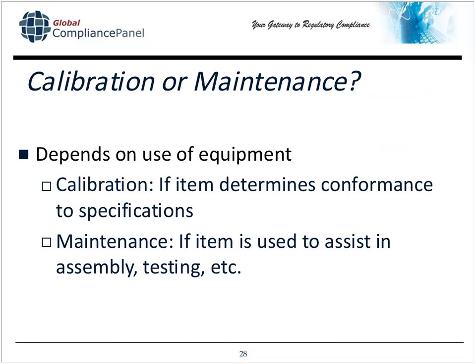Whether you maintain or calibrate depends on the use of the equipment. The way I like to distinguish is if the piece of equipment determines conformance to specifications, you're going to calibrate that. If it's used to assist in assembly testing, the phrase that's often out there is a manufacturing aid or tool or fixture. Fixtures and tools are normally maintained, but things that tell you whether or not a particular component, subassembly, or finished device is according to specification are calibrated. There's a little bit of crossover. Sometimes items determining conformance to specifications also undergo maintenance in addition to calibration, but it's more rare that a fixture or an aid is calibrated.